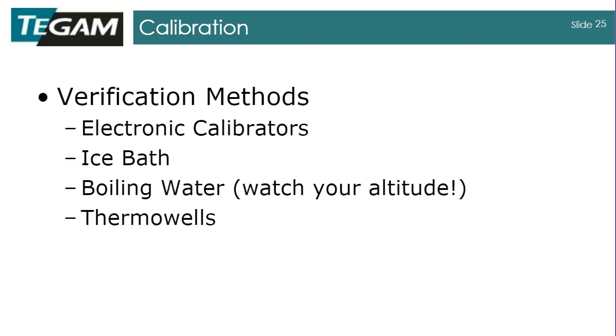But another concern is, if you're using a thermometer and it somehow gets damaged, you may not know it needs calibration for up to 6 months until you send it back. There are verification methods you can do locally. I've seen some people do these daily. That may or may not be necessary, but they're not hard. There are electronic calibrators that simulate temperature, so you can check your instruments with those.